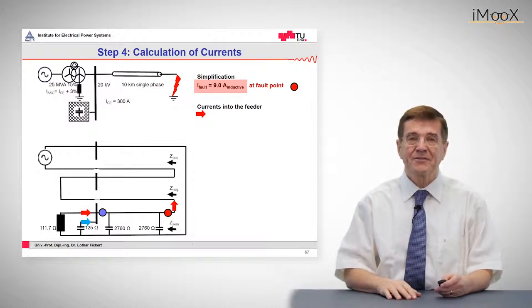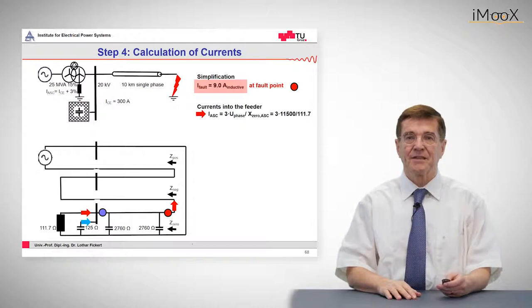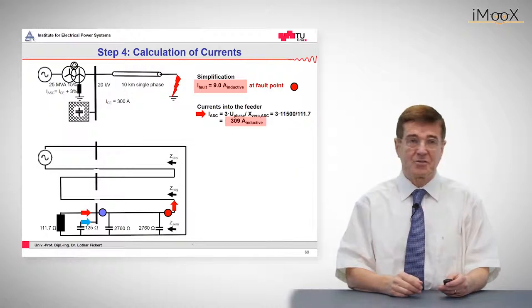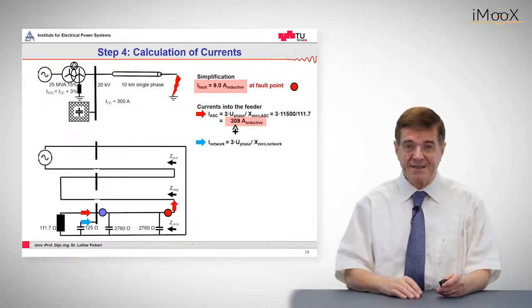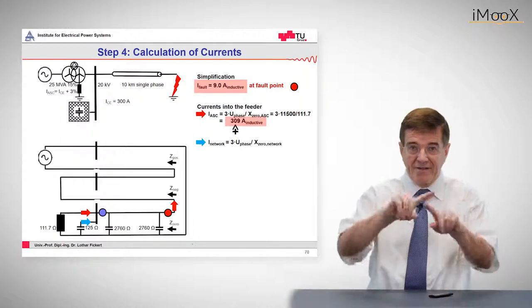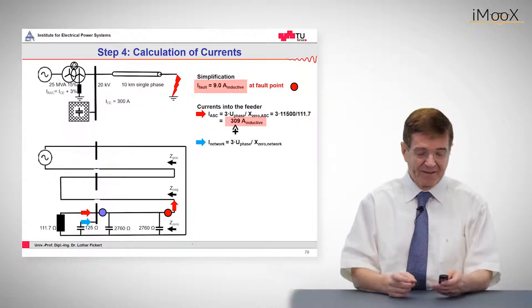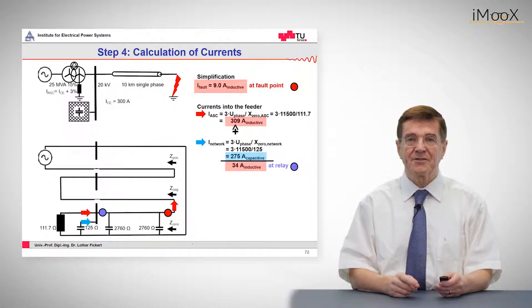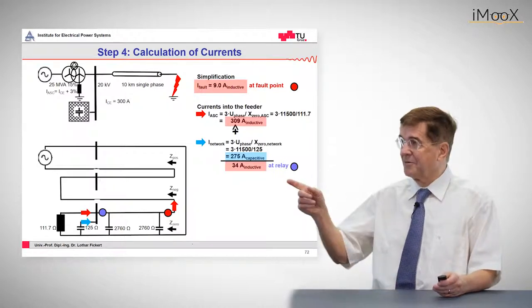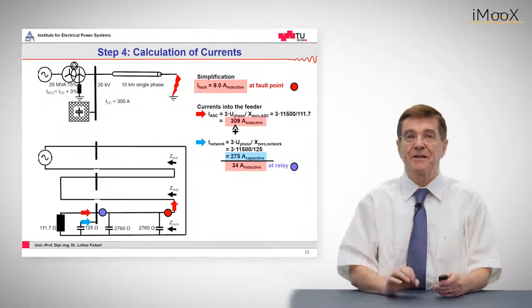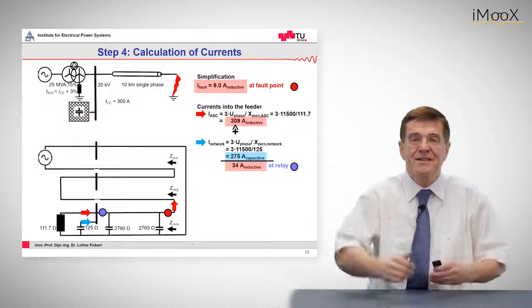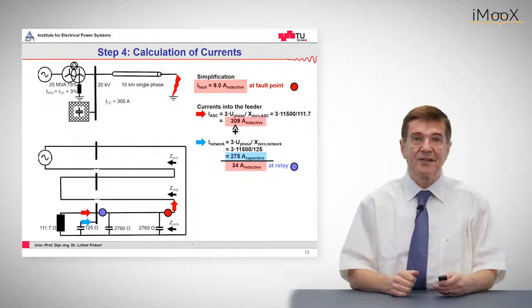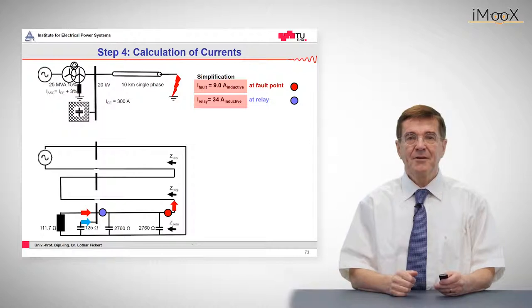First, the reactive current from the arc suppression coil comes out as, you can see here, as 309 amps, which was the set value. And for the capacitances we have to add this, according to the phasor law of addition, with a current of 275 amps. All together it's a current of 34 amps at the relay, which is not the same as at the fault point. And that must be kept in mind because this reduction in current, in reactive current, makes it difficult for the relays to find a good discrimination.